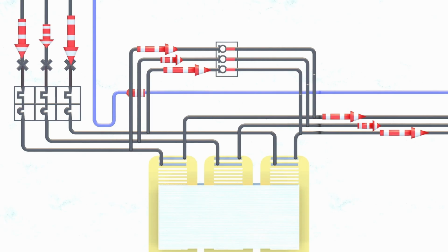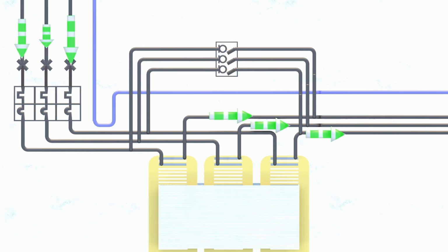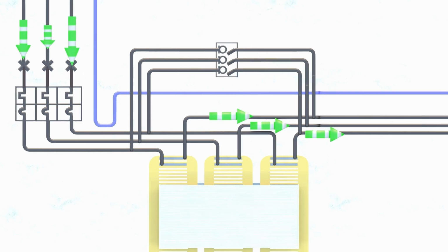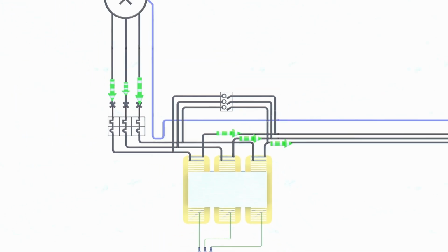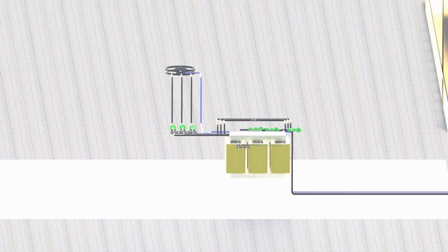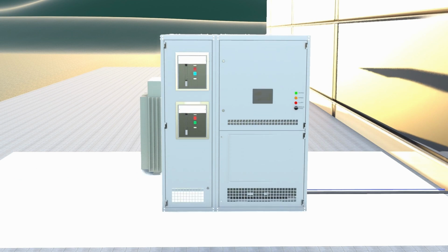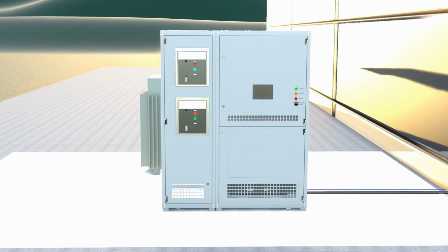In total, there are 288 switch circuits that are controlled within a span of 24 hours, ensuring that a change of operation occurs every 5 minutes throughout the day. With the resulting intervals of saving and bypass, the ECV measurement method can be carried out to measure the increase in efficiency and the reduced kilowatt hours.